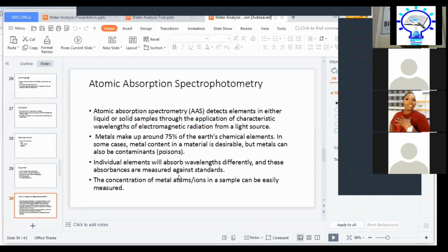So as for the atomic absorption spectrophotometer, what it does is measure the amount of metals that are in your water: calcium, magnesium, lead, arsenic, all these metals that can dissolve in our water and we keep drinking them. This machine will tell you the quantity, the parts per million that you have in that water. And then when we compare it with acceptable values, we know whether that water is good enough or not.